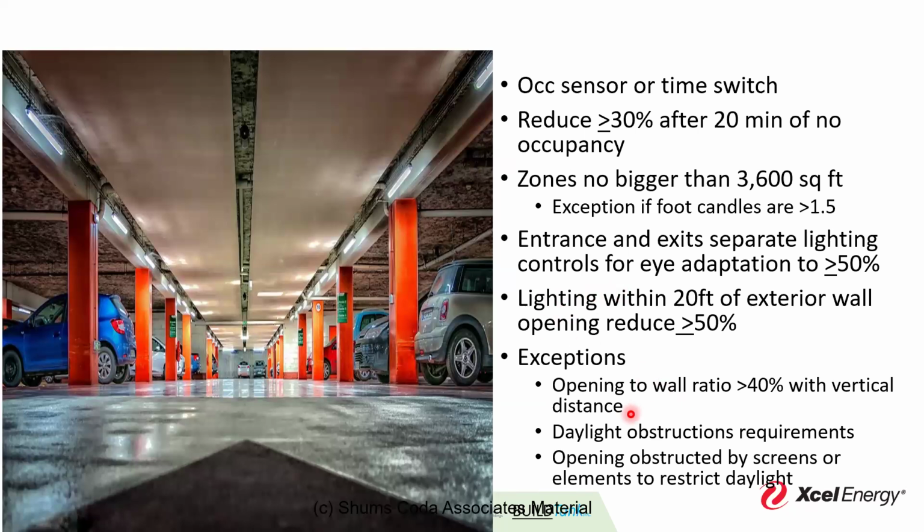We also take into account the wall ratios for the larger openings being a soft story here to figure out where we're going to be putting these reductions for the amount of lighting that we're allowed to have. Because we know that we should be getting either ambient light from the outside, sunlight during the day and things like that. And then deeper into the garage space where there is no daylight, that will be the places where you'll have that different expectation for running artificial lighting.